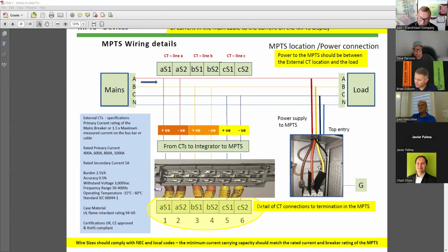Yes, you mentioned phase sequence. You are messing up the phase sequence on one side, and on the other side, you've got two parts, right? These CTs, the expansion for CT is current transformer. You have two sets of coils. One is measuring the true power, like 700 amps, and the second wire is picking up 5 amps. So when you just swap positive and negative because it was laying on the wrong side, or you had wrong connections done, you're actually messing up the functioning of the CT itself.